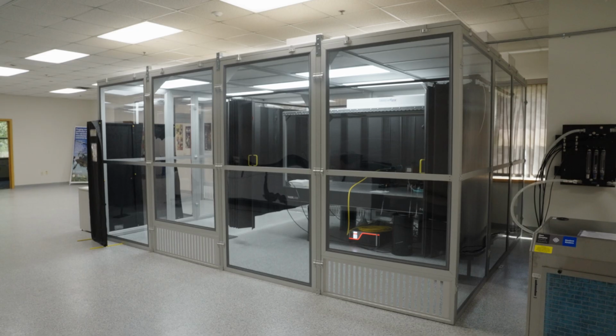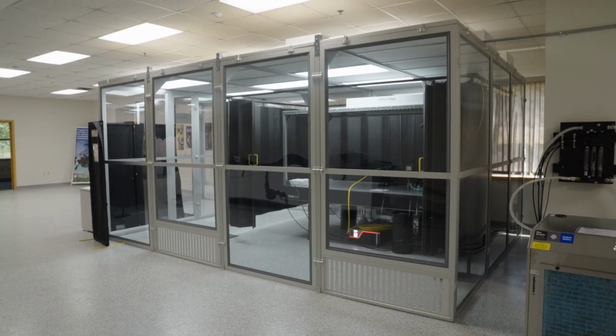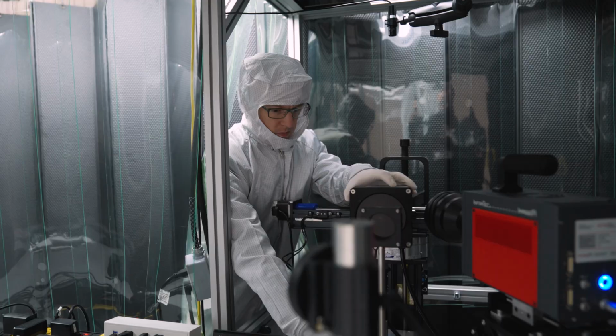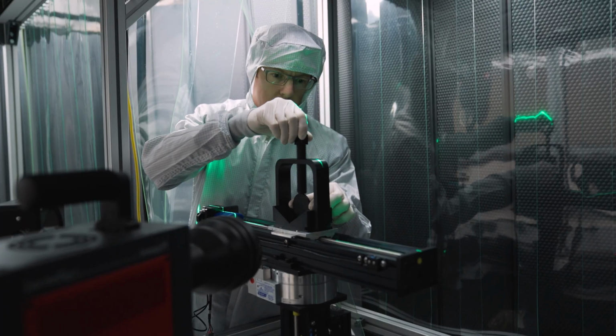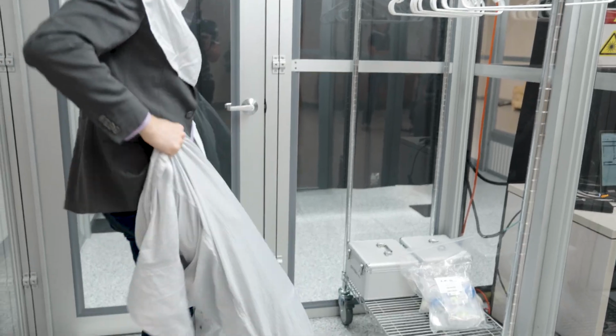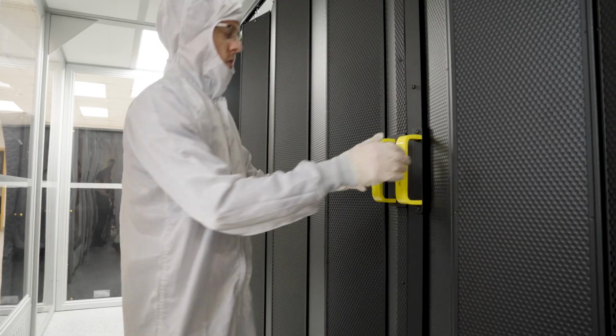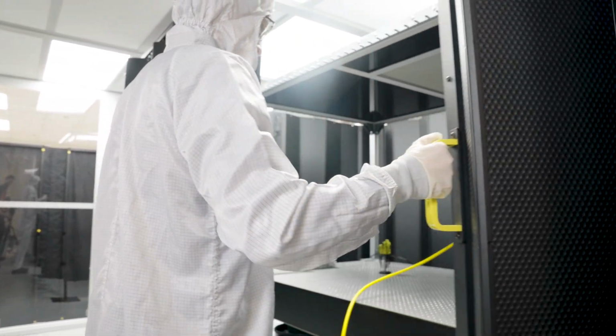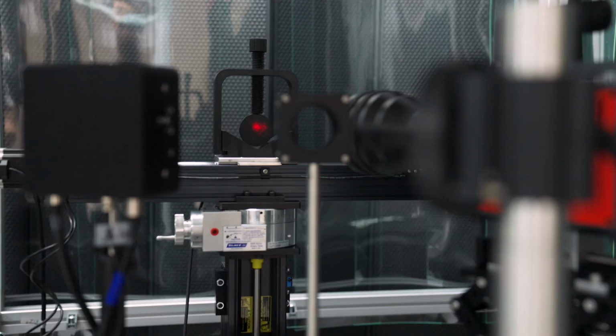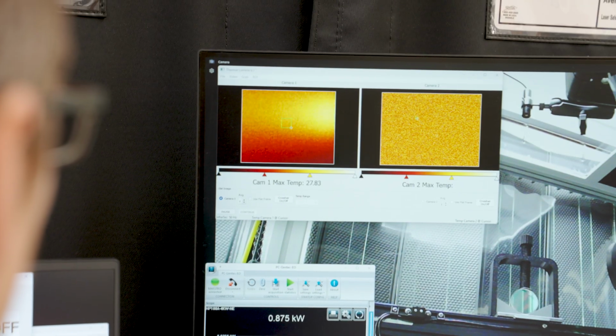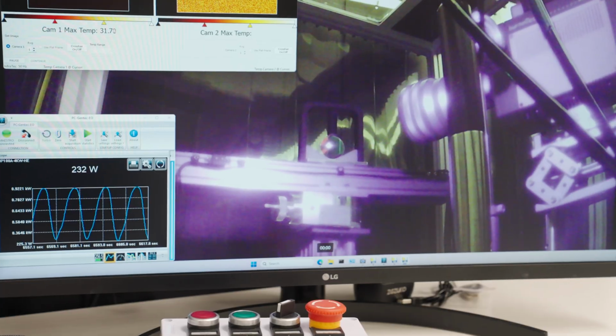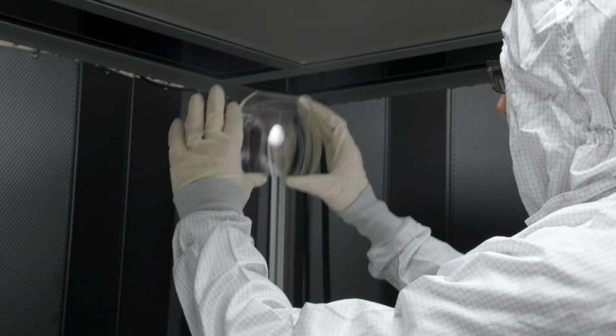This is our high-energy laser metrology optics station. It is used to test high-energy laser optics that go into military and other sorts of high-energy laser optical systems. We've got a nested clean room to make sure that there's no dust or particulates that can get on the optics. We scan a high-energy laser beam across an optical surface, and we look for hot spots with an infrared imager. We're using this to be able to test all those optics before they're built into the full system to make sure they won't fail in the field.